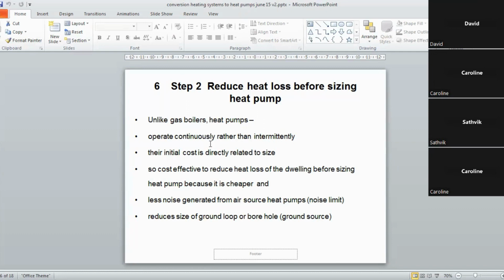The rationale behind that is, first, when we think about the characteristics of the heat pump systems, as Rayner mentioned, heat pumps work at very low temperature compared to the gas boilers that are traditionally installed in the UK building stock. When we reduce the temperature of the central heating system from, for example, a typical 70 degrees to something around 50 degrees C, it means that if we don't reduce the energy demand of the building, probably we need to increase the area of heat transfer, which has an implication on increasing the surface area of the radiators, changing the circulation pumps, and so on, which all of them together are very, very expensive.